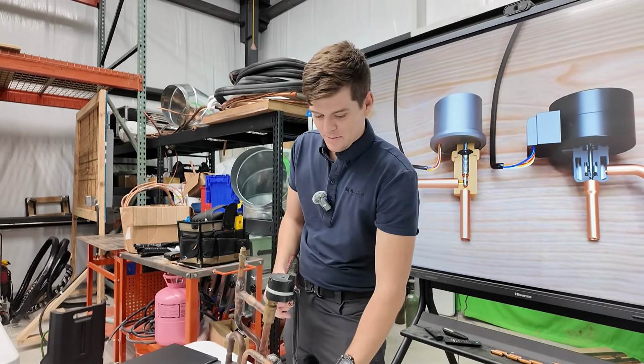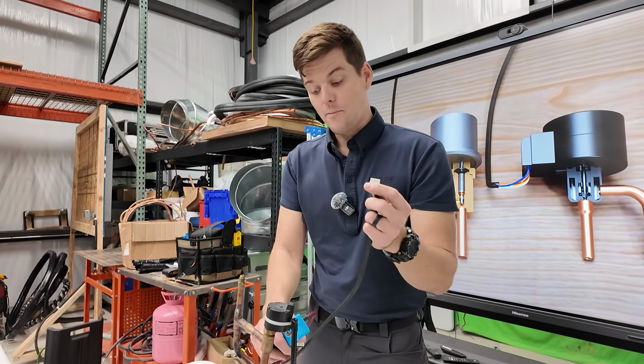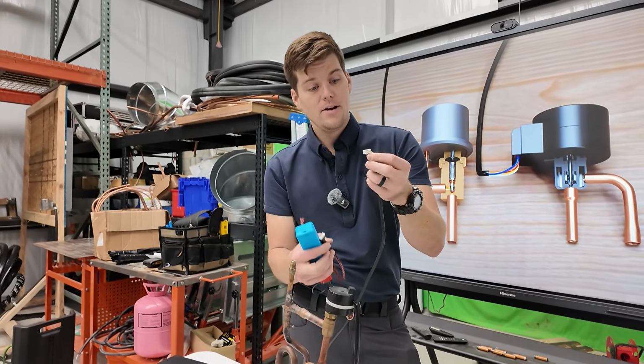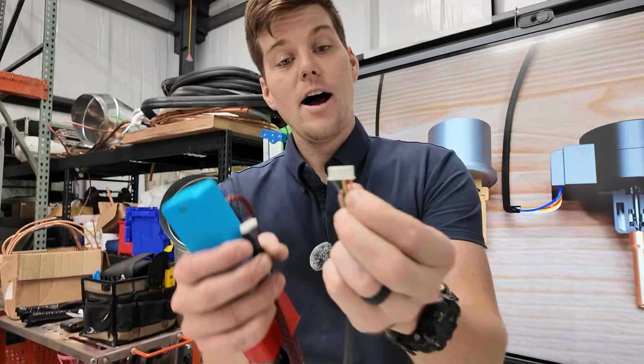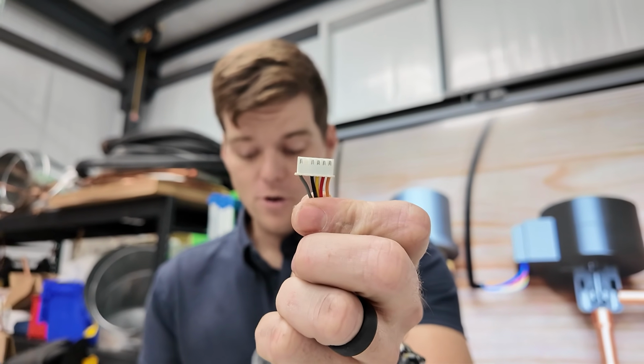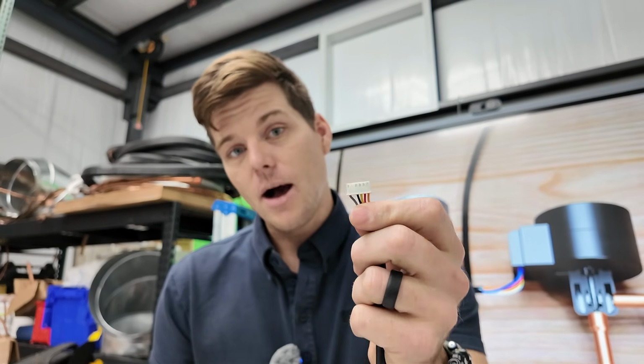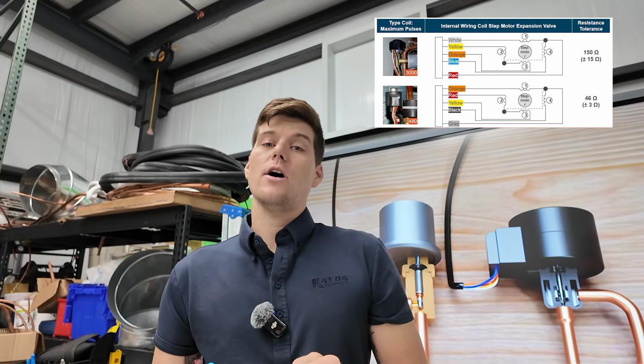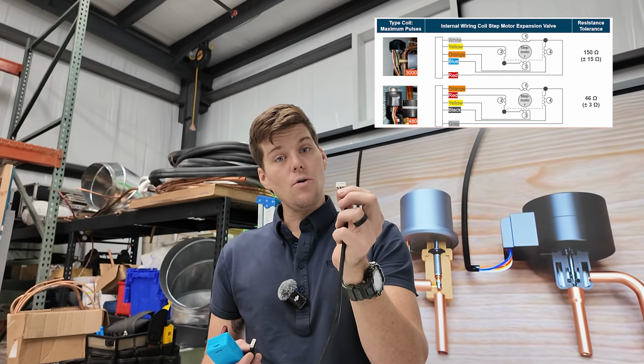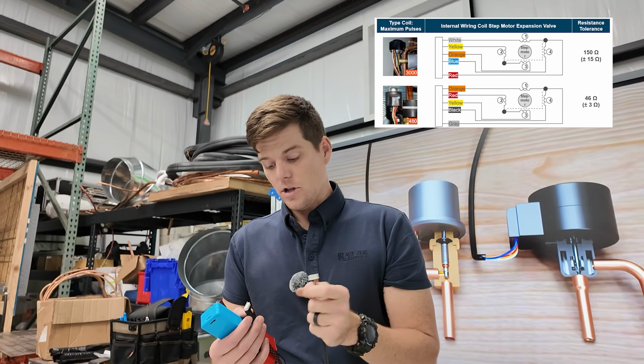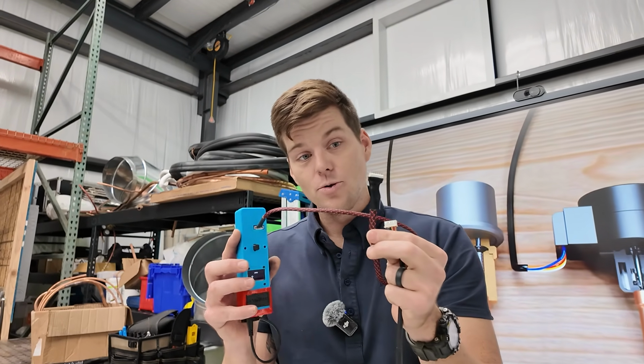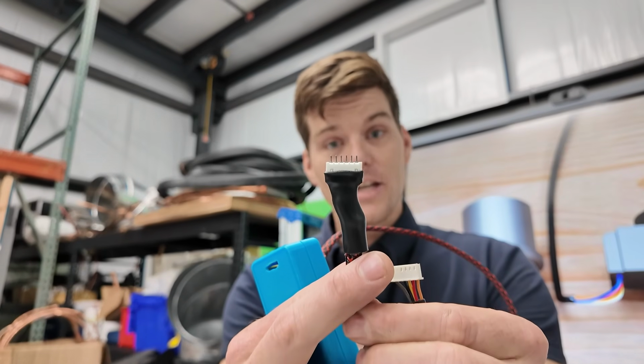With this demonstration, we're going to take the wire from our indirect drive down here at the bottom. You'll notice there are 5 wires, and one wire is spaced out apart from all the others. That wire is our common wire. Always reference the service manual to understand what windings go in what order and where the common wire is located. On my EEVMate tool, I have a cable with 6 prongs.